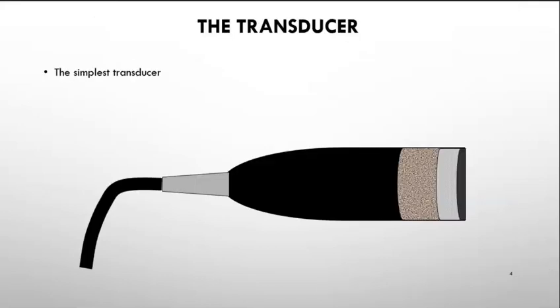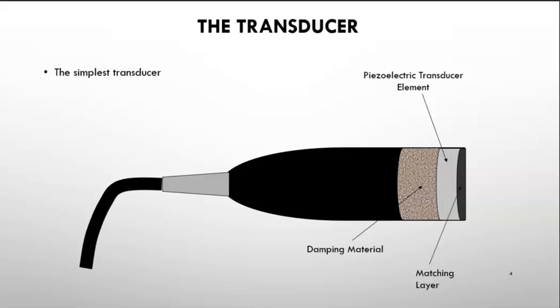So the simplest transducer we can have is one that simply has the piezoelectric material near one end, and behind it is some damping material to stop the vibration of the piezoelectric, and in front of it is what we call a matching layer that makes up the front of the transducer. Behind the damping material is a case that holds it, and then you have a strain relief which keeps the wires from pulling on each other too hard, and of course a cable which connects the transducer to the machine that you're going to be using.